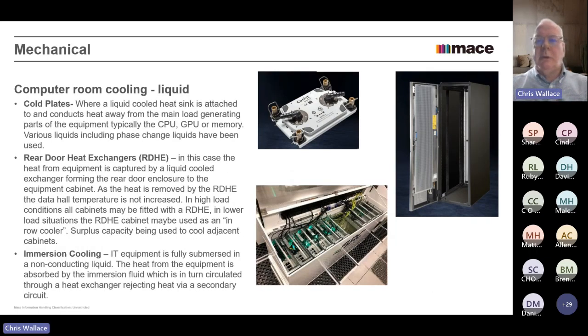So with liquid cooling, you're going to have two slides with the same pictures and the same titles, but the words are slightly different. So, some sorts of liquid cooling. The top one is cold plates. Basically, this little white device is designed to be like a heat sink. It sits on top of whatever the GPU, the CPU, or the memory in the computer is, and you run a liquid through it. It could be some form of purified water, or some form of silicone oil, or it could be a phase change liquid. There are different liquids being used, but the idea is that you liquid cool the chip where the heat is itself.